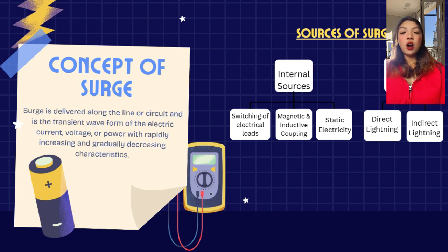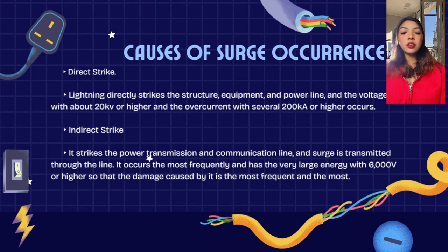The next slide is the causes of surge occurrence. There are two major causes, the direct strike and the indirect strike. The direct strike is when lightning directly hits the structure, equipment, or power lines, and produces very high voltage, around 20 kilovolts or more, and a very high current up to hundreds of kiloamperes. This is rare but extremely destructive. Second is the indirect strike. Lightning hits nearby areas, not directly the structure. The surge travels through power lines and communication lines. It produces voltage around 6,000 volts or higher and occurs more frequently than a direct strike. Even if lightning doesn't hit directly, it can still damage equipment through connected lines.